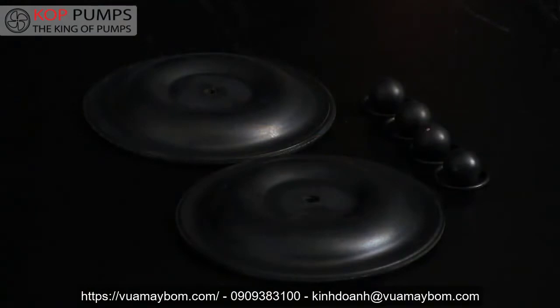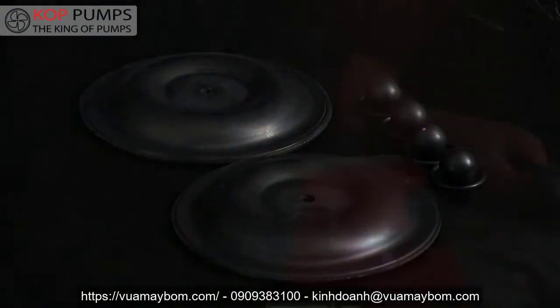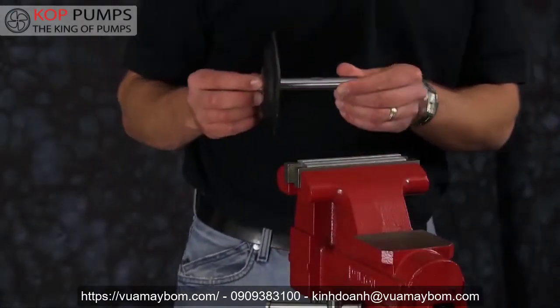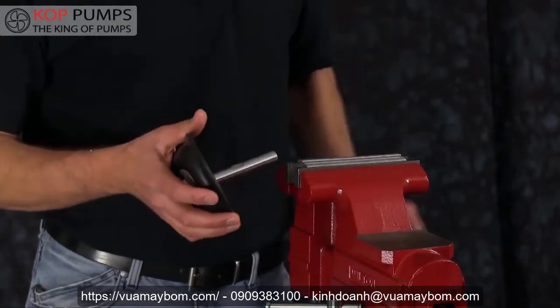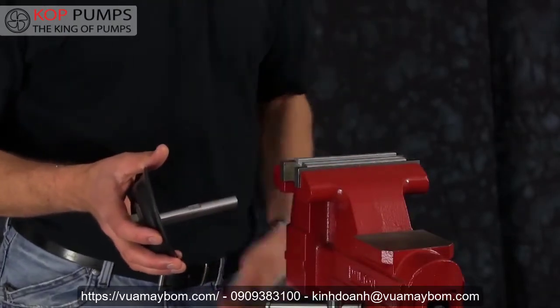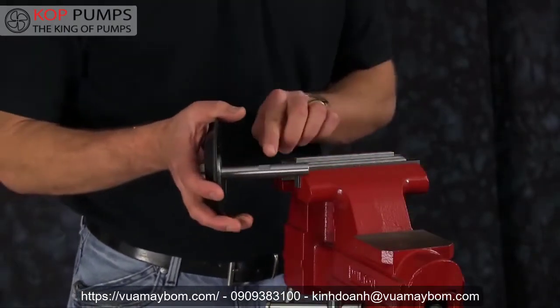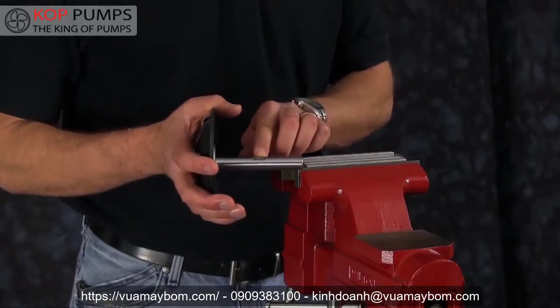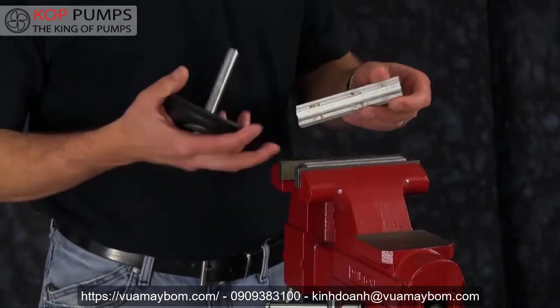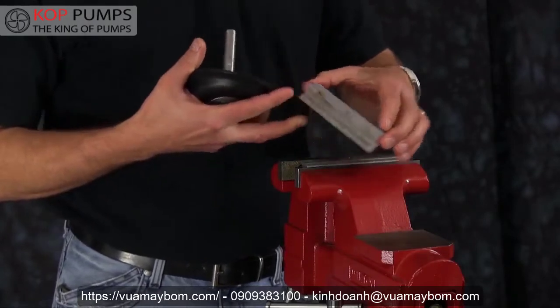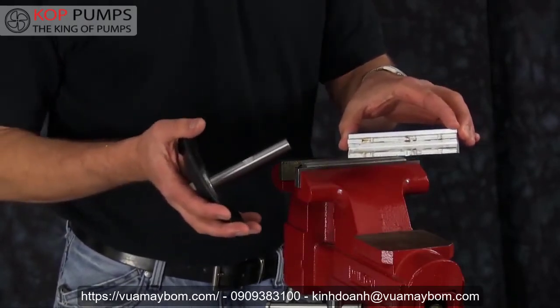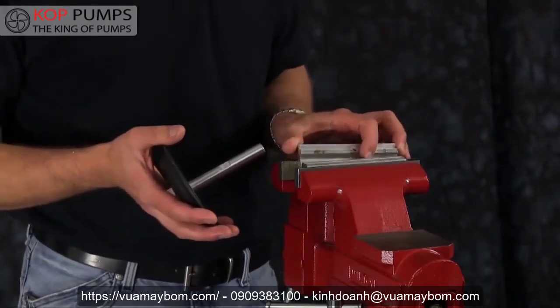Open the wet end kit and lay out components for rebuild purposes. Versamatic shafts have wrench flats on the rod to assist in diaphragm removal and installation when performing maintenance in the field. Today we will use a vise with soft jaws. Soft jaws are utilized to ensure that the shaft is not scarred, scratched, or damaged while the shaft is clamped in the vise.